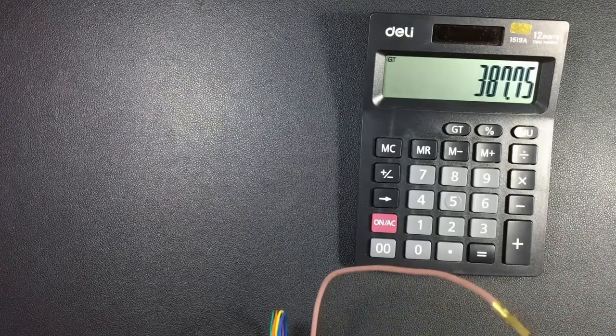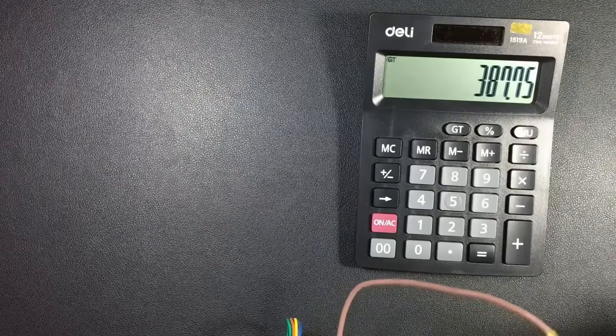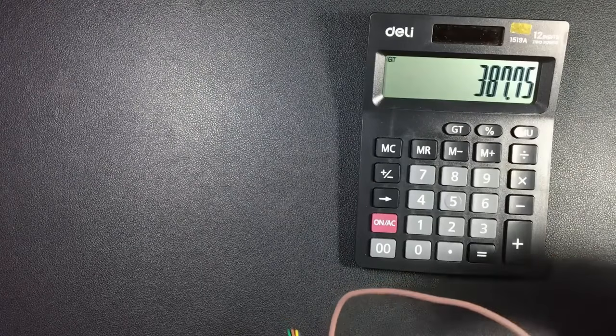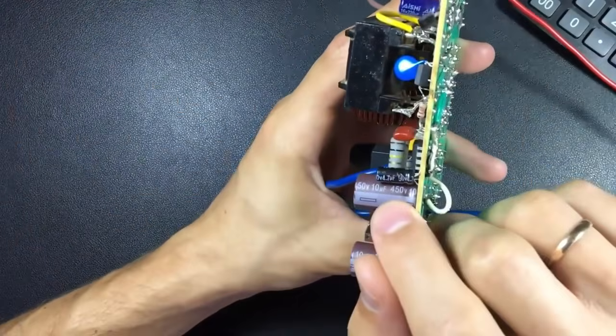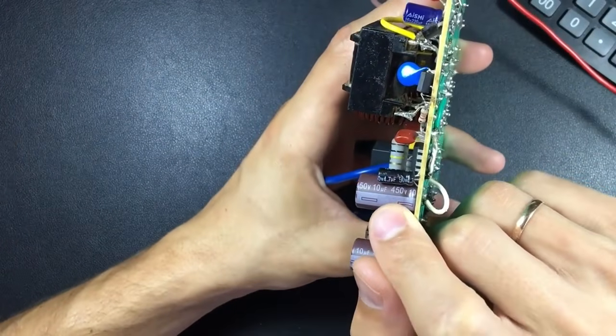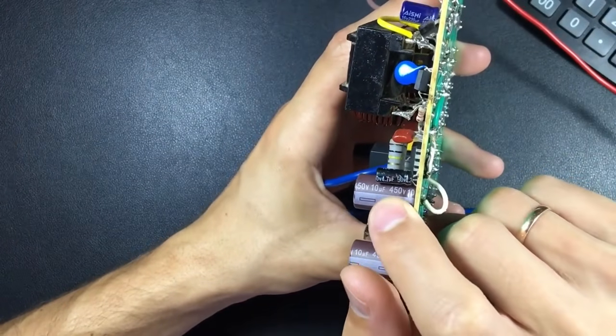25% more, we multiply it by 1.25, and we are talking about 387 volts. The next standard value of capacitors is the value that the manufacturer will place. In this case, it can be seen that they obtained 450 volts, so they used 450 volt capacitors.